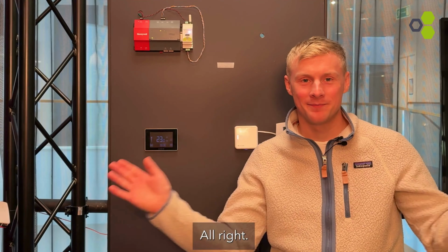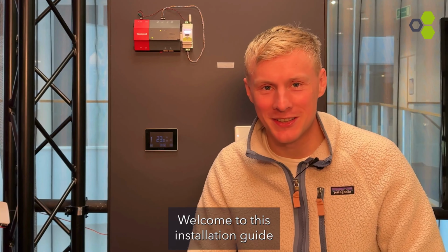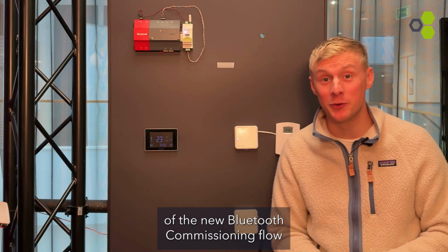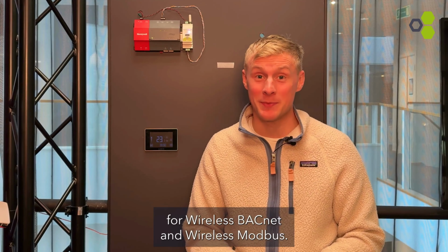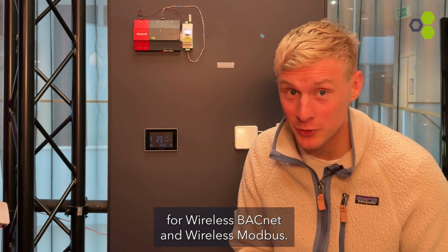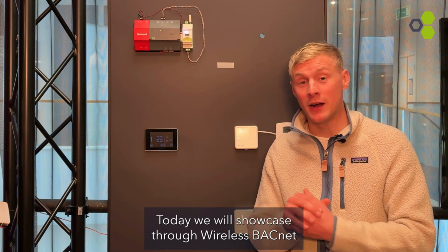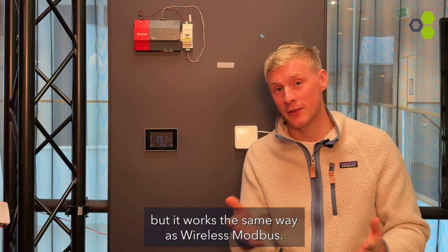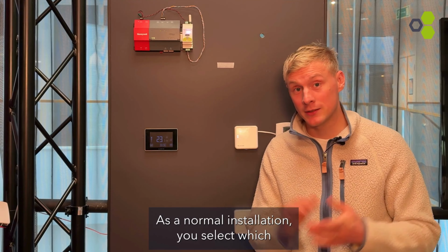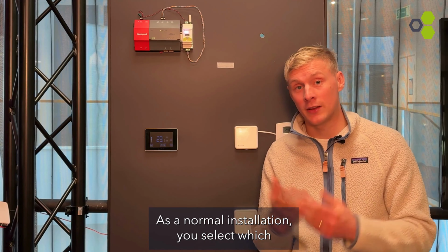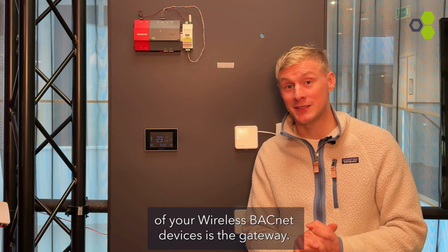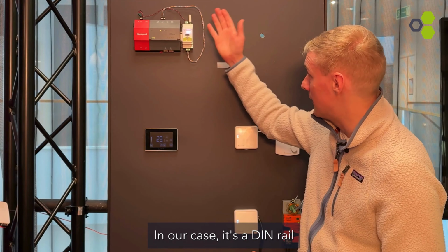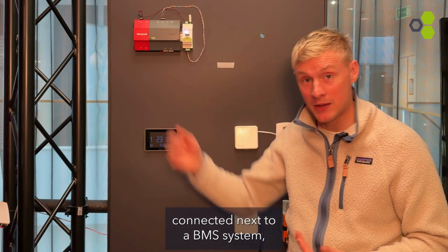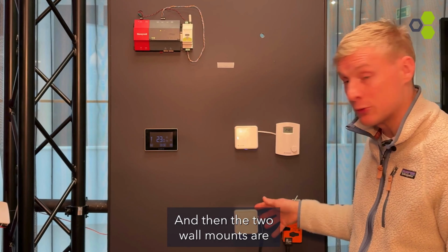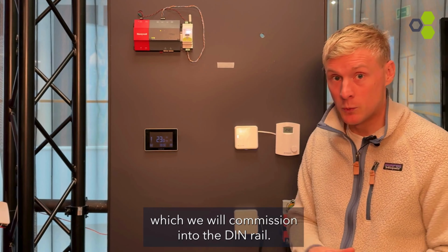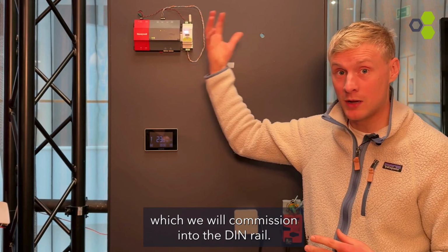All right, welcome to this installation guide of the new Bluetooth commissioning flow for wireless BACnet and wireless Modbus. Today we will showcase through wireless BACnet, but it works the same way as wireless Modbus. As a normal installation, you select which of your wireless BACnet devices is the gateway. In our case, it's a DIN rail connected next to a BMS system. And then the two wall mounts are connected to BACnet devices, which we will commission into the DIN rail.